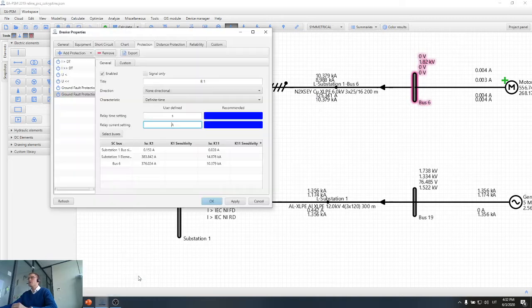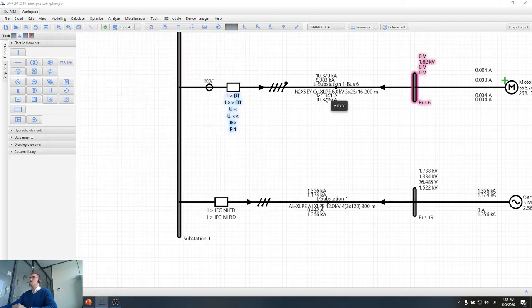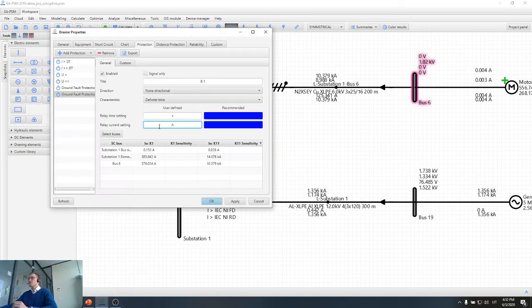So we need to set a current which is actually not bigger than the rating, but smaller than the zero sequence current, with enough margin to maintain selectivity. So I will provide something like, let's say, 150 amps, and the relay time setting I will provide quite small. We can set here like 100 milliseconds.